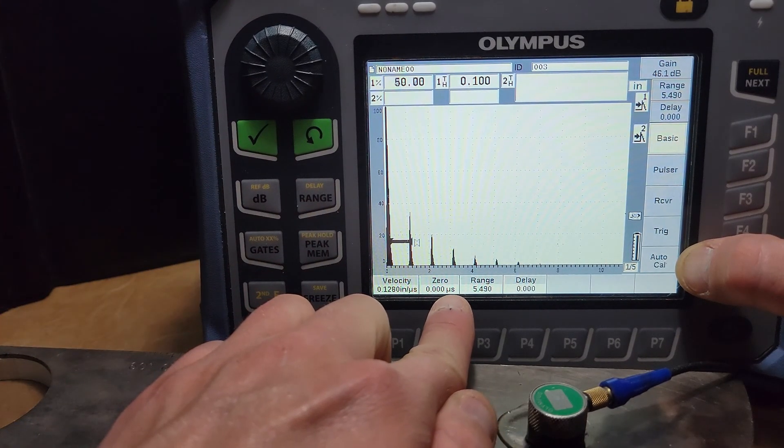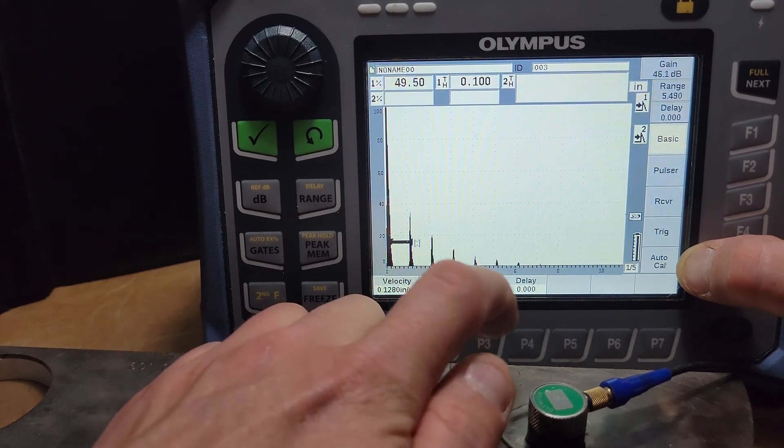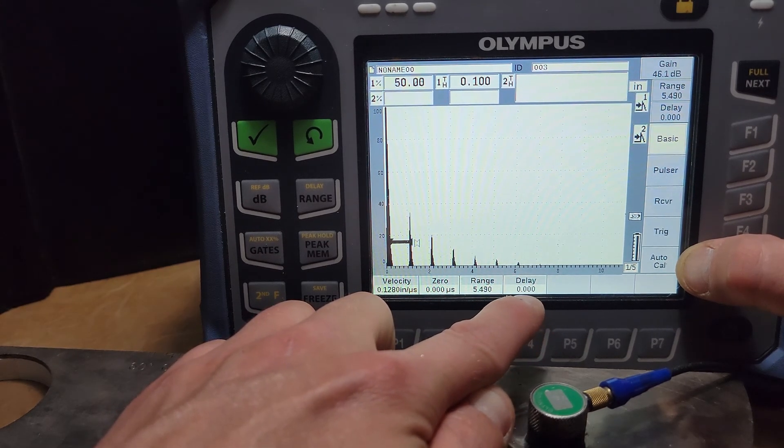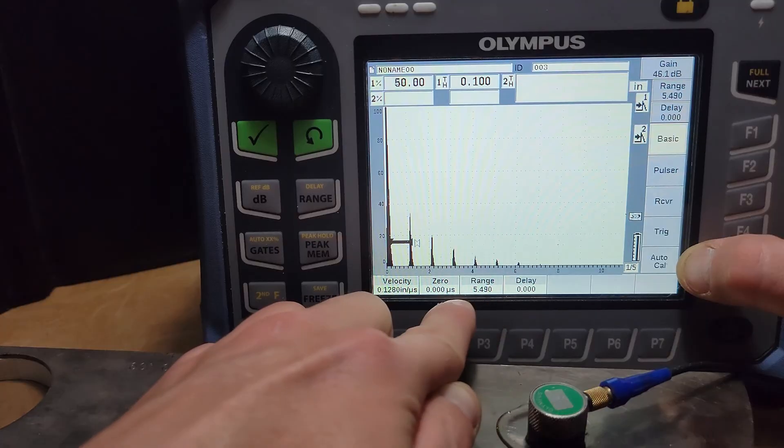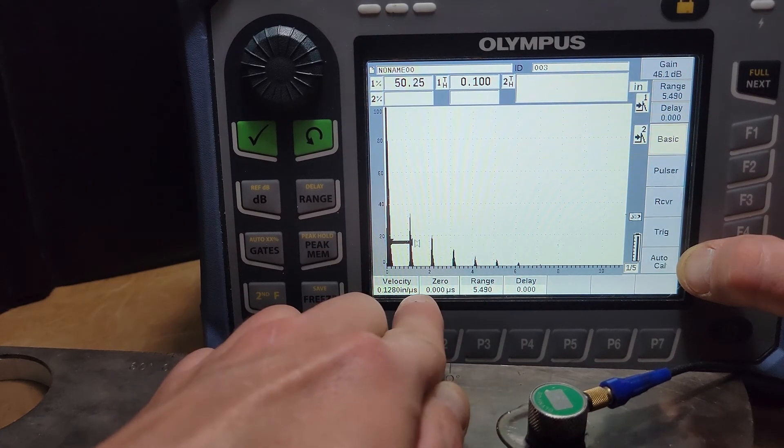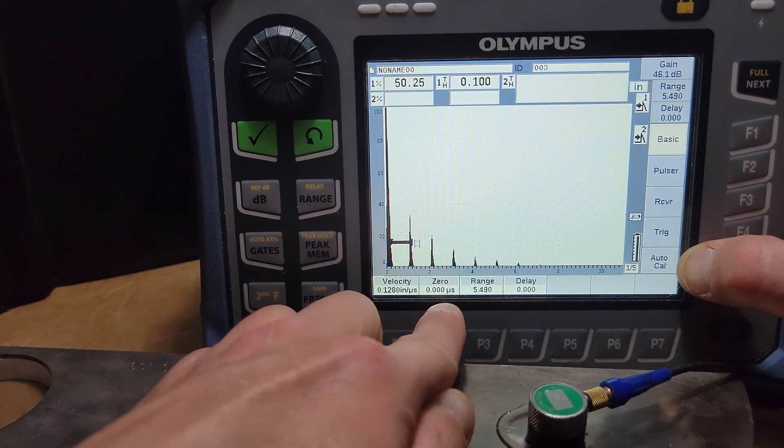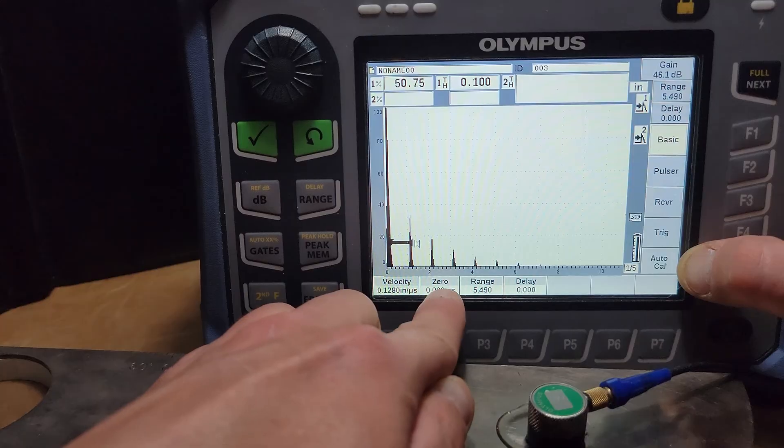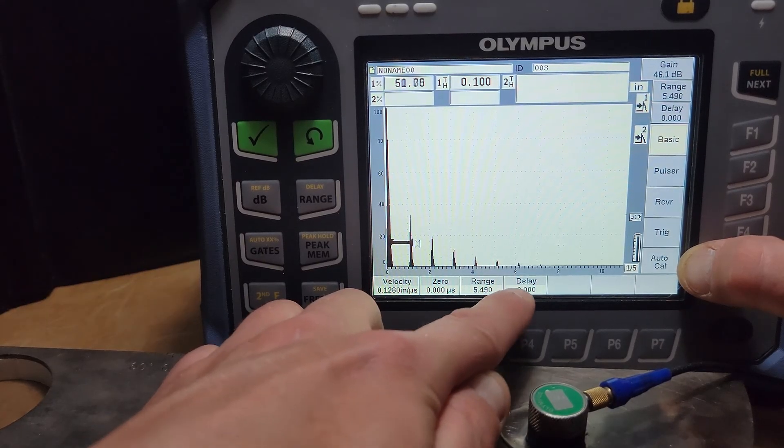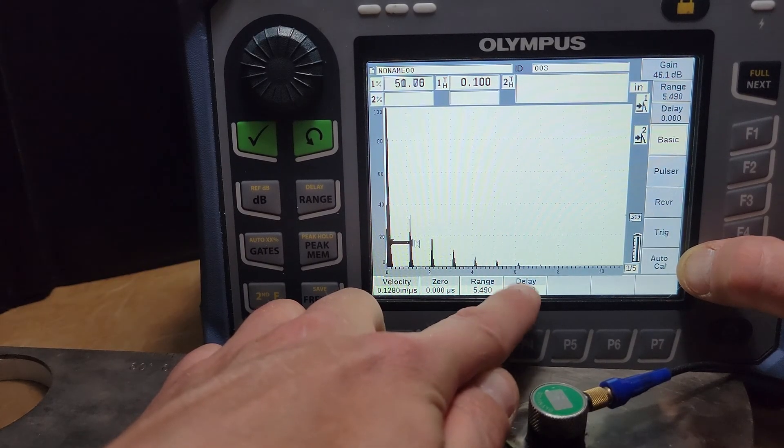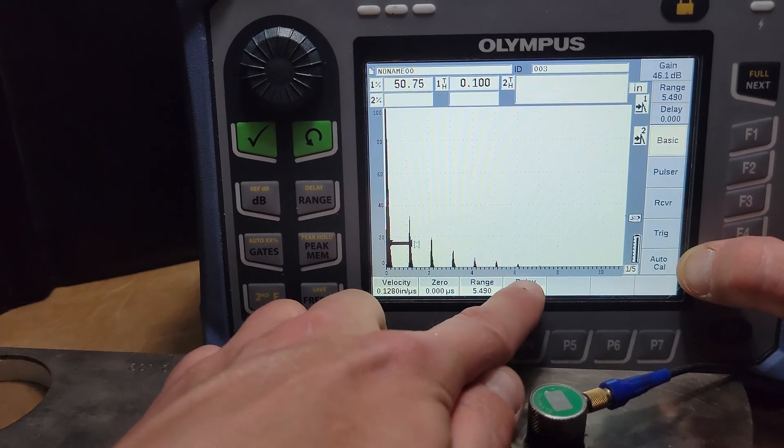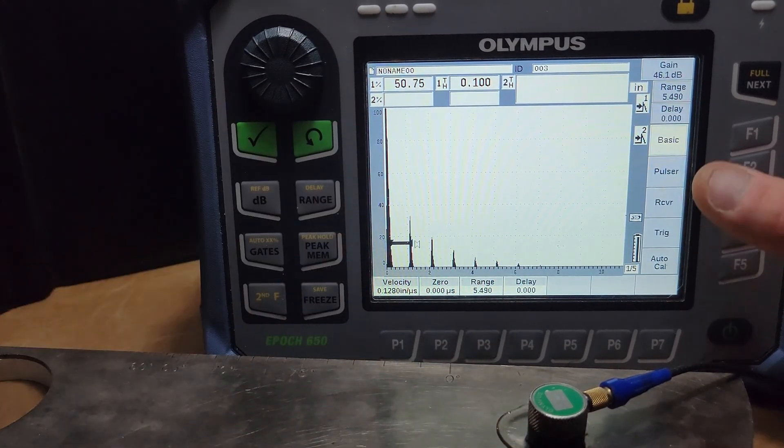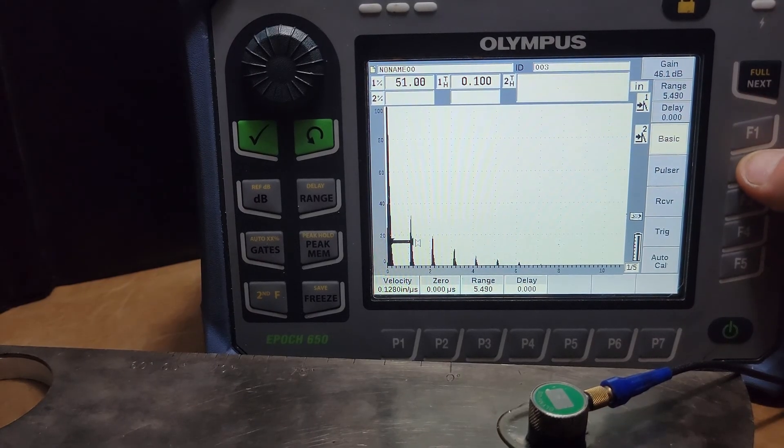The way to tell the difference between zero offset or probe delay and display delay is notice its unit of measures in microseconds and so is the velocity, so this will actually impact measurements. This will not, this one will lead you into a land of confusion, avoid this one unless you are specifically using it for a good reason.